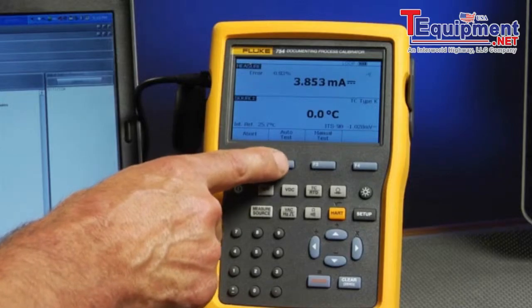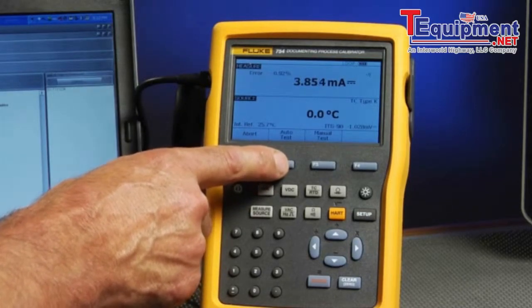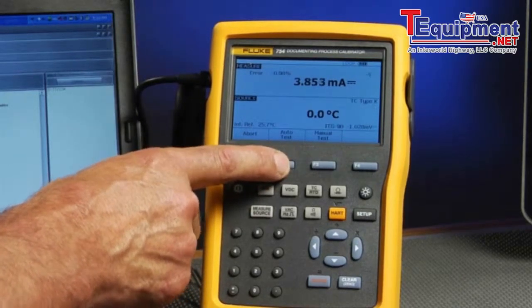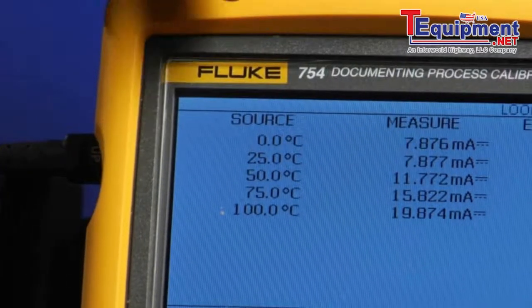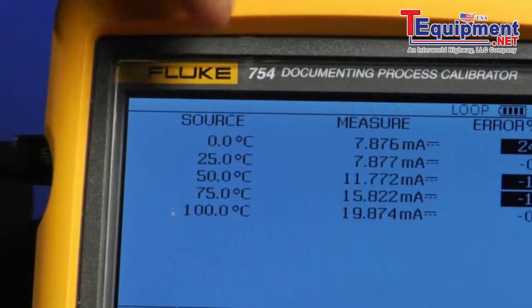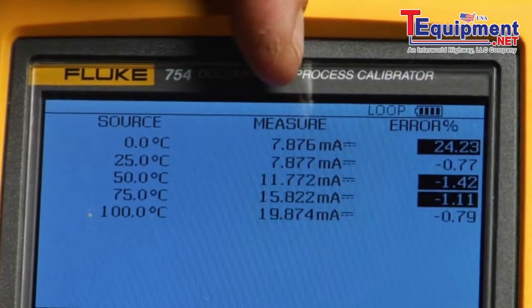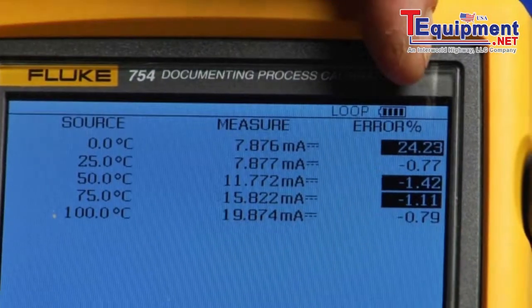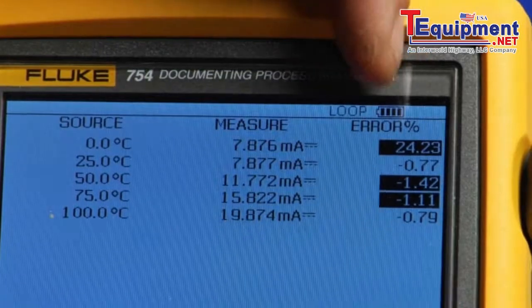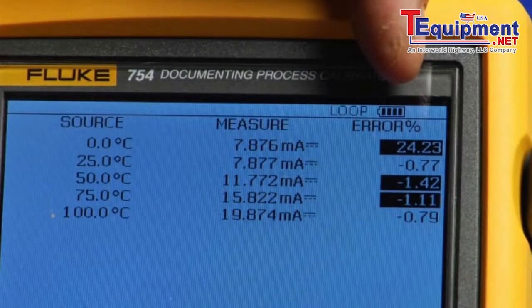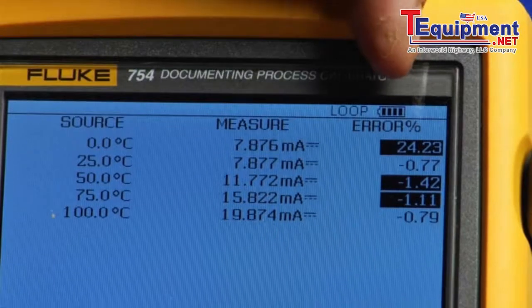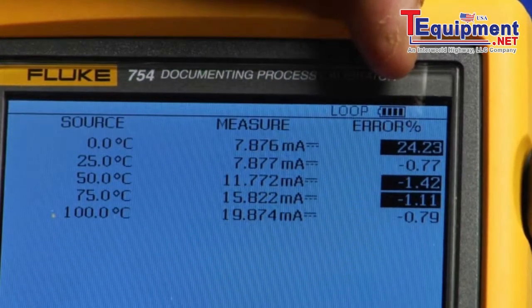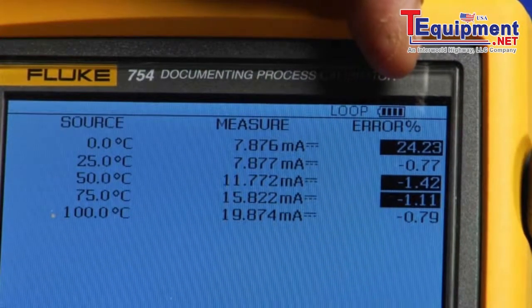Then select auto test to automatically document the performance of the transmitter. So here you see the recorded temperature values that were applied, milliamp values that were measured, and the errors percent of span. If the error percent of span is found greater than the test tolerance, it's flagged in reverse video. In this case, this indicates that this as found test of this transmitter has failed.